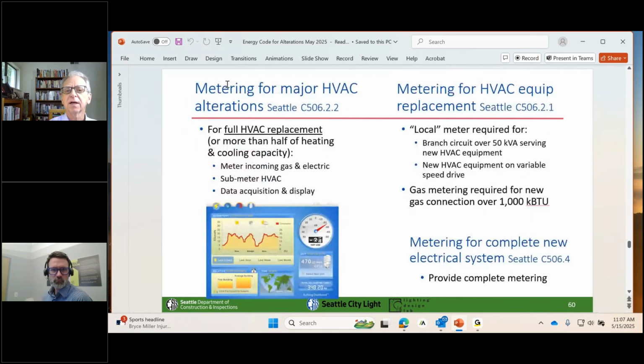Metering is required in alterations first for major HVAC alterations. So if you're doing an overhaul that involves more than half of your heating or cooling capacity, then you're going to need to set up metering to meet the code requirements for the incoming power and gas and sub-metering for the HVAC system with the normal data acquisition system. If you're just doing one piece of equipment and not doing this whole system replacement, then you'd need the kind of meter that you'd put on a piece of equipment where you'd have to come around with a clipboard and write it down. It wouldn't be tied into an overall system.